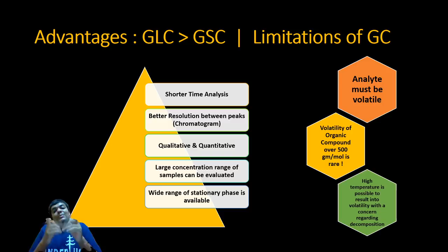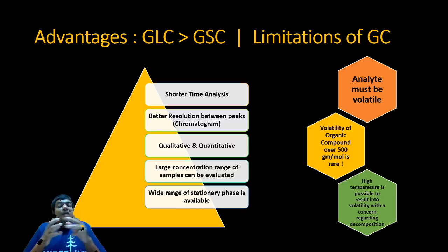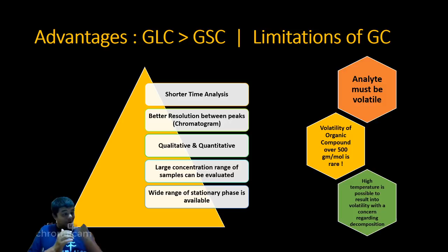Analyte must be volatile. You cannot use a non-volatile analyte. Second important thing, volatility of organic compounds over 500 grams is rare. It means most of your samples should be below 500 grams. And sometimes there are macromolecules which generally are not accepted that easily by GC. They go with HPLC or they go with gel permeation or such combinations, but they do not fall in gas chromatography. They fall in the earlier category of liquid chromatography, or rather to say the huge HPLC family.